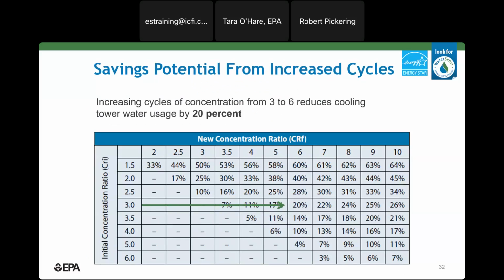So this chart on the slide shows the type of savings that you can achieve by increasing your cycles of concentration. You read the initial concentrations on the left across the new cycles on the top. And so, for example, improving from 3 cycles to 6 cycles would provide a 20% savings in cooling tower water use.